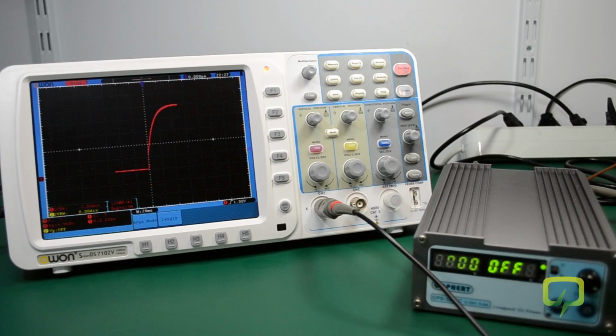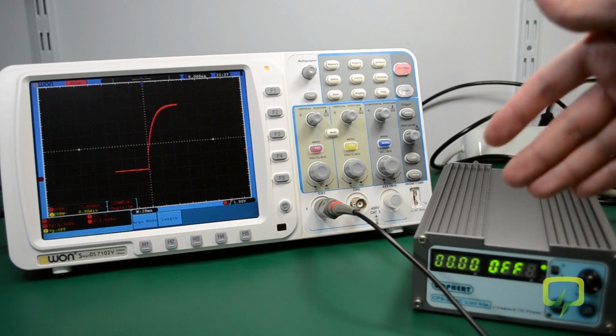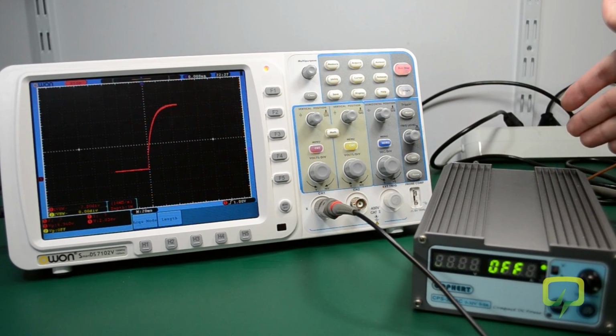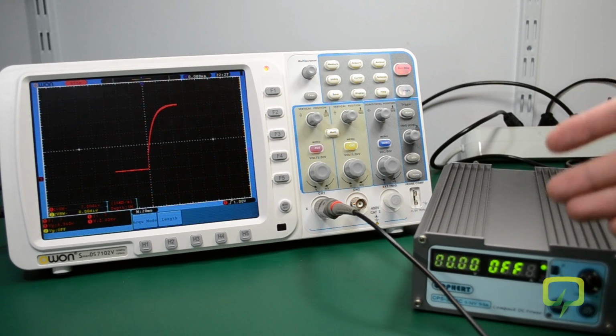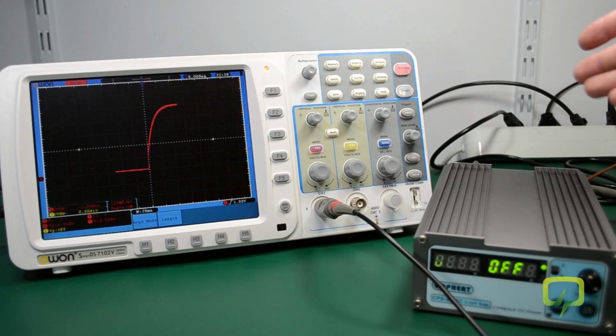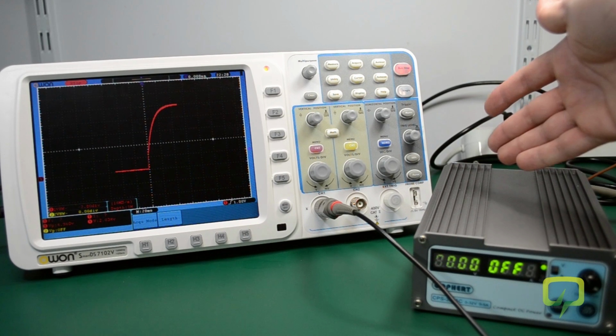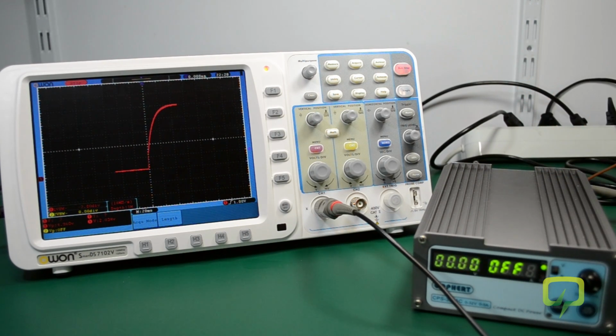For this next test, I'm going to use my scope and test if this power supply overshoots when it is turned on. First, I'm going to test the soft on-off button. I don't expect it to overshoot in this mode because the power supply is already internally regulating. It's just that it has its output disabled, and turning the output on will just connect the output sockets to the already regulating power supply, so I don't expect it to overshoot in this mode.